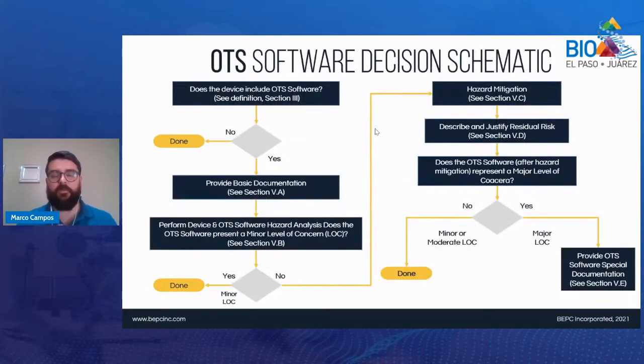So this is a quick schematic, again directly from the FDA guideline. It's going to walk you through how do I know if my device, or my software rather, classifies as off-the-shelf software, and then what do I need to do to validate that piece of software. FDA provides a very thorough guideline on this, and this is just a quick summary of what they mention. But in a nutshell, if you have off-the-shelf software, you need to provide a basic set of documentation, which is essentially what the software is, the version of it, the platform used to run it, and so on and so forth.